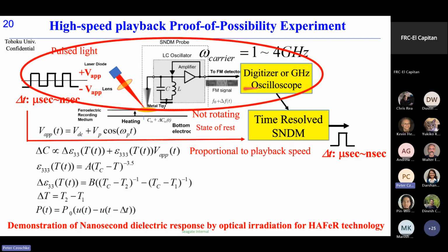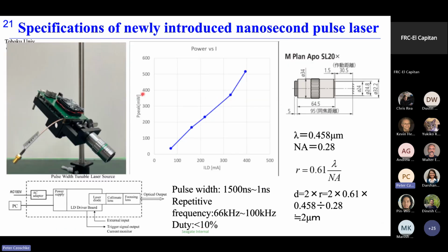And at first, we constructed the hardware, and in this case, we introduced a new laser pulse system, and the pulse duration can be varied from 1.5 microsecond to 1 nanosecond, and the frequency is from about 66 kilohertz to 100 kilohertz. And the wavelength is 458 nanometer. The beam diameter is about 2 micron.